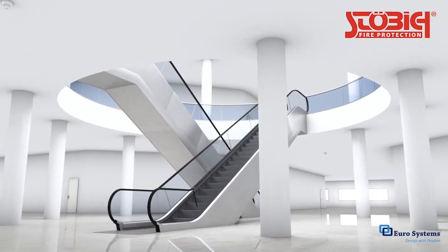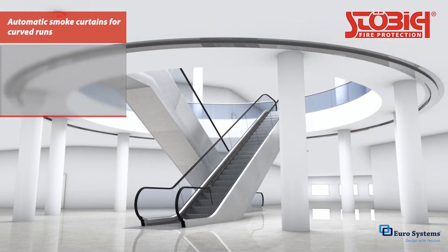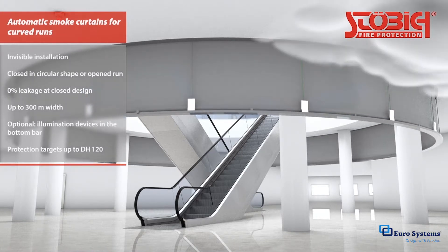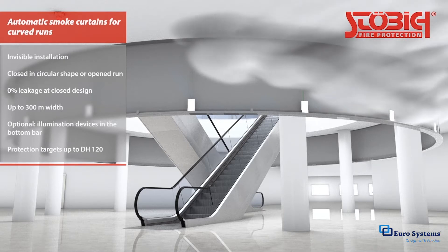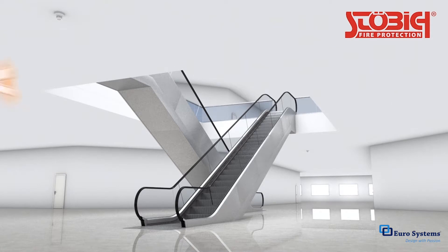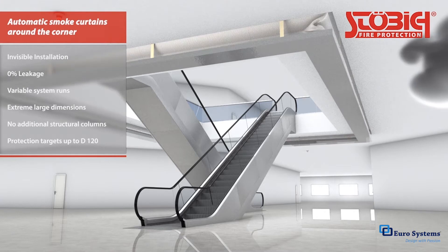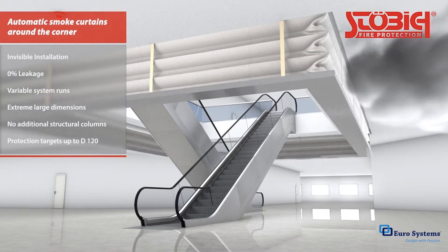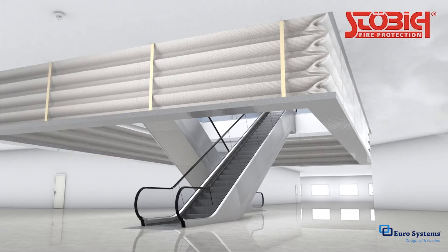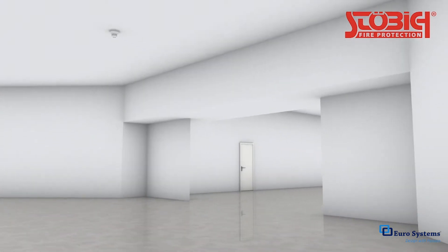Conventional fire curtain systems are unsuitable for use on round or elliptical openings. For these situations, Stöbich offers special curved smoke curtains in an open or closed design. The fabric is gathered and stored above the suspended ceiling. Smoke curtains around corners satisfy the high demands of any smoke extraction concept, as well as special architectural and design needs. The way the textile is gathered makes it possible to protect polygonal areas too, without gaps and without requiring additional support in corners.